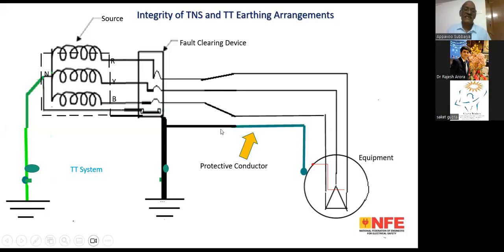Here, what we can see is this fault current will necessarily have to go through the general mass of earth. So there will be earth resistance constituted by your own earthing system and the source, that is the supplier's or your own transformer earthing system. It will be in the order of, say, 10 plus 10, 20 ohms. Instead of milliohms as in the TN-S system, you will have several tens of ohms. So the fault clearing device will see a much lower current. It may not trip. That is why the regulation provides RCDs for the TT system. So these are the basic principles.